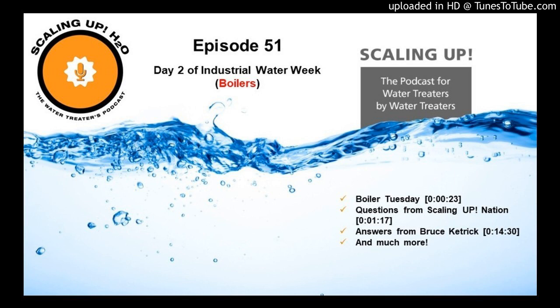9 times out of 10, when I try to investigate issues with corrosion in boilers, it's normally an operation issue, or more importantly, a lack of operation issue. So let's say that we're designing a new facility and we've got to figure out what type of boilers to put in there. Well, we know we're going to do more business, so why not buy a bigger boiler than we need so we can take care of those orders we need to fill 3, 4, 5 years from now? Makes sense, right? We just buy it once and now we don't have to totally retool the entire system.